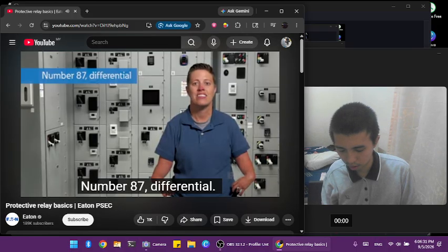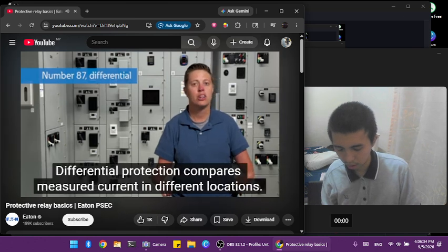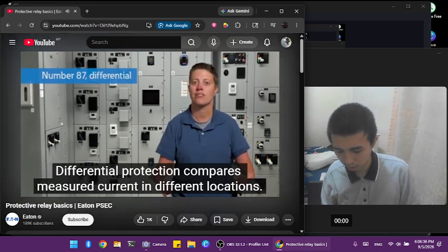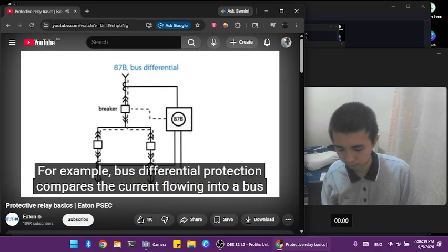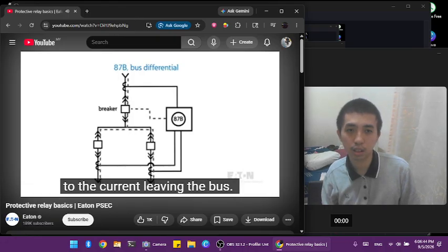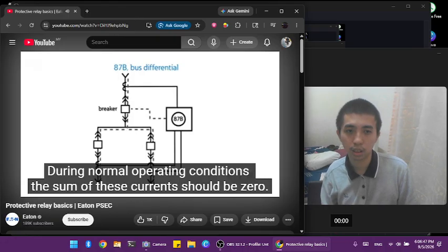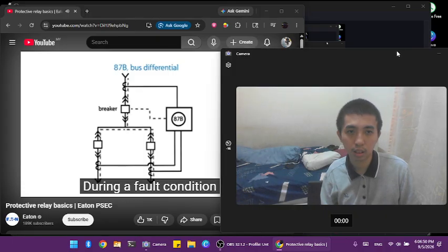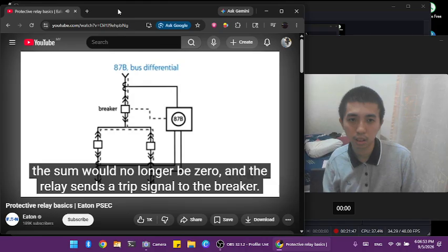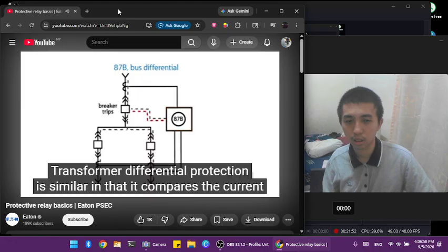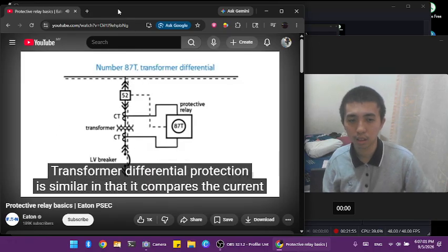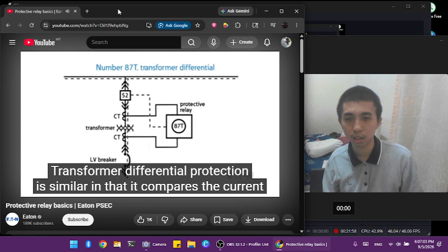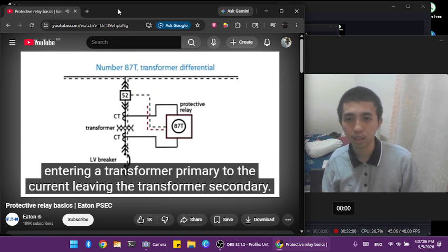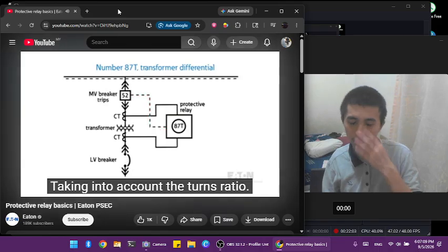Number 87, differential. Differential protection compares measured current in different locations. For example, bus differential protection compares the current flowing into a bus to the current leaving the bus. During normal operating conditions, the sum of these currents should be 0. During a fault condition, the sum would no longer be 0, and the relay sends a trip signal to the breaker. Transformer differential protection is similar in that it compares the current entering a transformer primary to the current leaving the transformer secondary, taking into account the turns ratio.